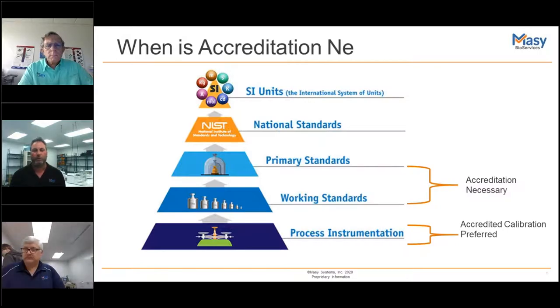The critical measurement of the device could be the transmitter, or a number of other things. Those devices used to measure it, you'd want to focus on having the best measurement possible. But as far as a go/no-go gauge, just a visual indicator of a pressure gauge, it's probably not necessary. You're not building any data off it, not using it for a batch record or anything like that. You're just using it as a physical indicator to say the system is operating as it should.